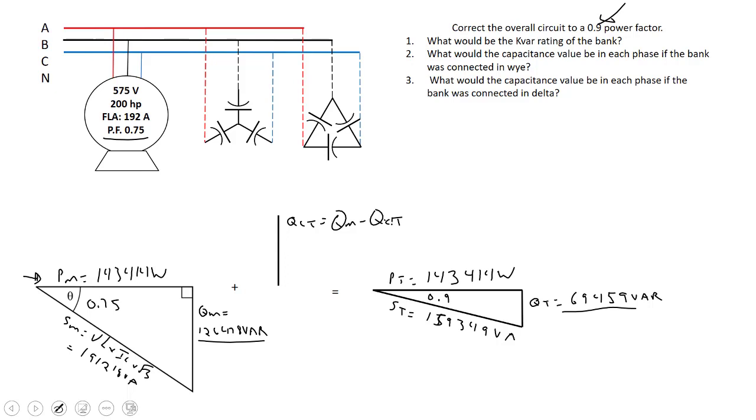So that's going to be if I take 126,478 VAR and subtract off 69,459, we come to about 57,019 VAR. So the first question, what would be the KVAR rating of the bank required to correct the circuit to 0.9? We're looking at about a 57 KVAR bank.